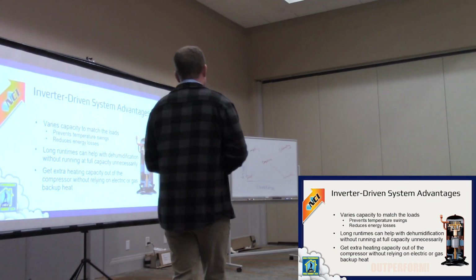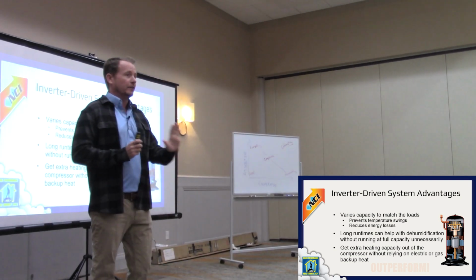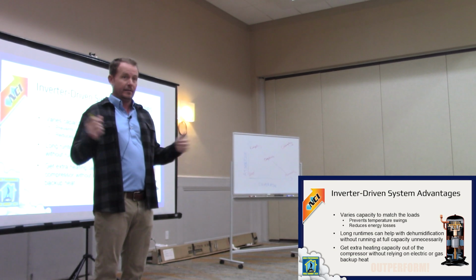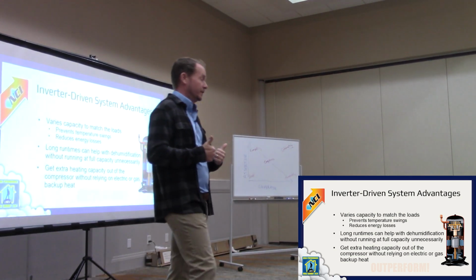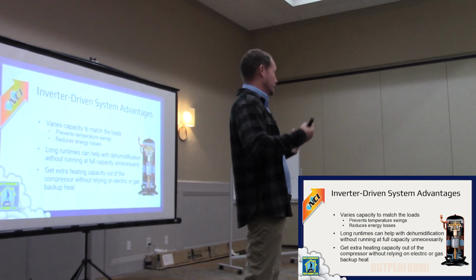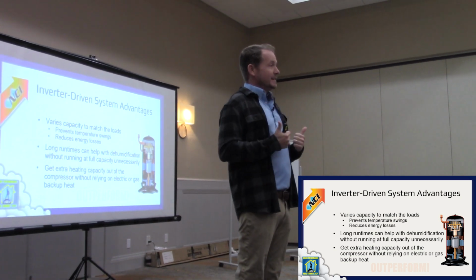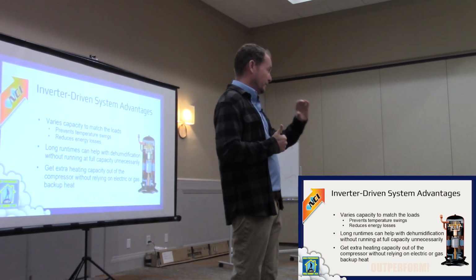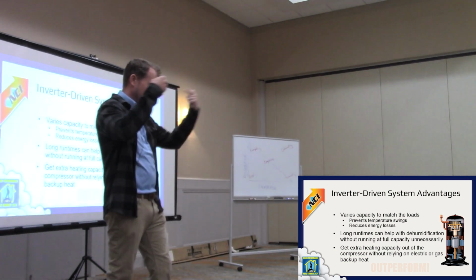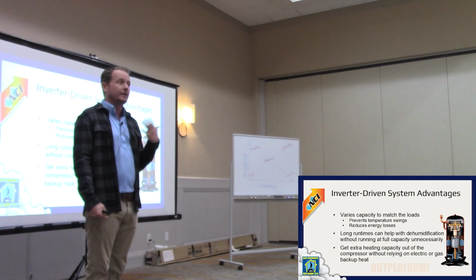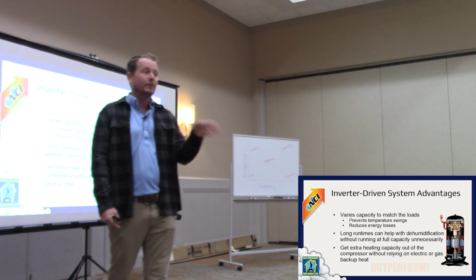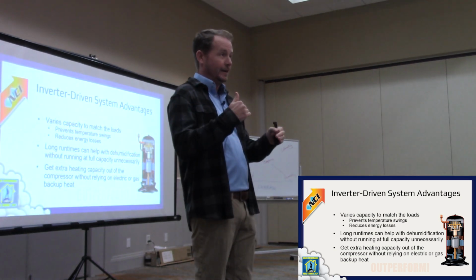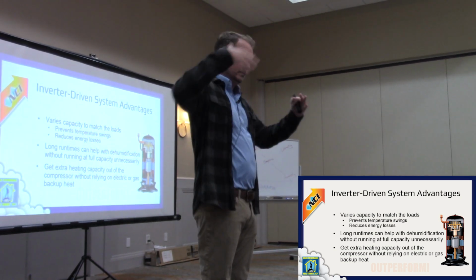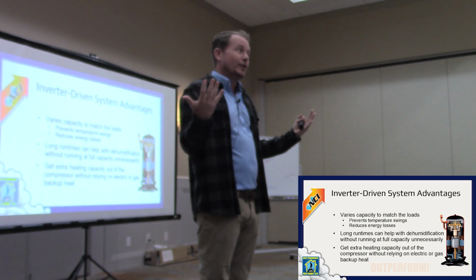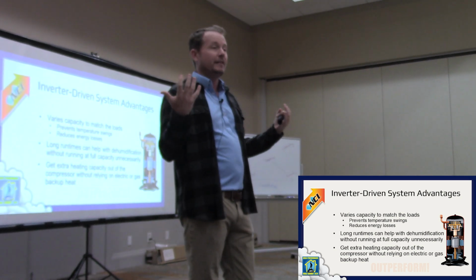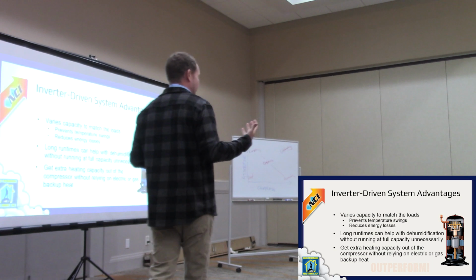Make sense? So, inverter-driven equipment is very good at running a lot. That's great, thumbs up. We want equipment to run a lot. We want it to run all the time if we could help it, right? Unless there's absolutely no load on the structure. Downside is sometimes they're not great at keeping a cold evaporator coil when they've turned down, when the compressor's spinning slower. And that's something you need to know about your equipment. Problem is most equipment manufacturers don't give you data on how well they dehumidify when they're turned down. They give you when it's run full bore, right? So you've got to do that testing yourself. If you're having issues dehumidifying with your equipment, then that's what you need to look at.